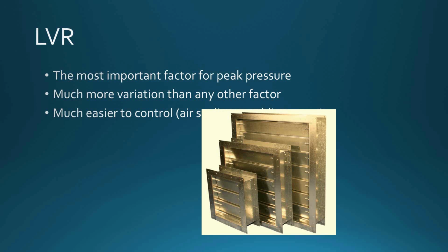So the leak to volume ratio is the most important. It's fairly easy to control, and if we find that we have an excessive pressure, which we will be able to determine with our free vent analyzer, which we'll look at later, we may need to install a vent. I know it's been standard procedure in the U.S. to often install vents for all inert systems, and often that's required, but interestingly, you'll find out sometimes it's not required. And to never install vents for halocarbons, and often it is required for halocarbons, and it's not installed. So I would say that halocarbons require vents maybe 25% of the time, and in some jurisdictions they are not being installed at all. And I think that is a problem.